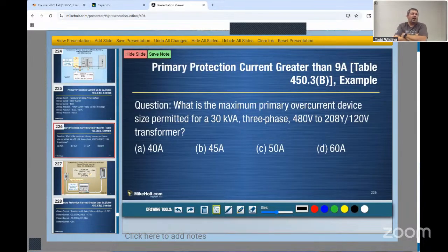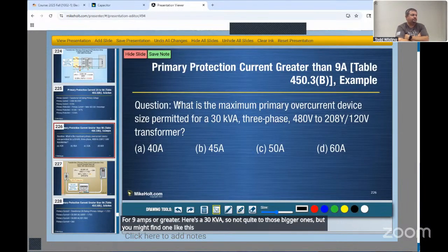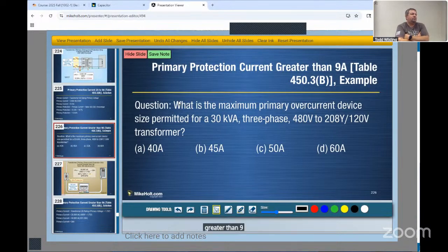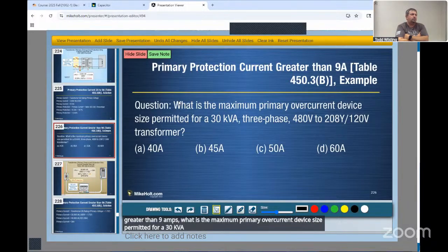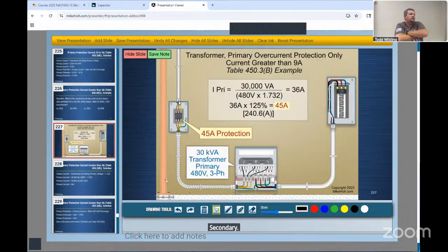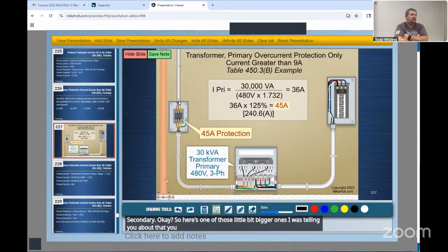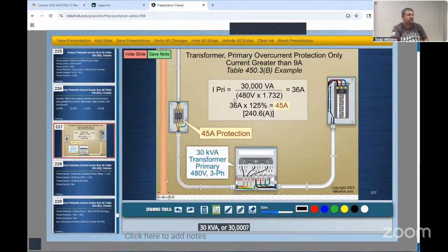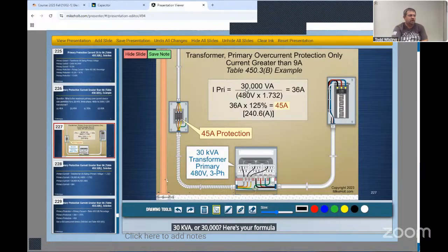For 9 amps or greater, here's a 30 kVA. So not quite to those bigger ones, but you might find one like this, a little bit smaller. Greater than 9 amps, what is the maximum primary overcurrent device size permitted for a 30 kVA, 3-phase 480, 208, 120 secondary? Okay. So here's one of those little bit bigger ones I was telling you about that you'll typically see. 30 kVA or 30,000. Here's your formula, how it shows you.